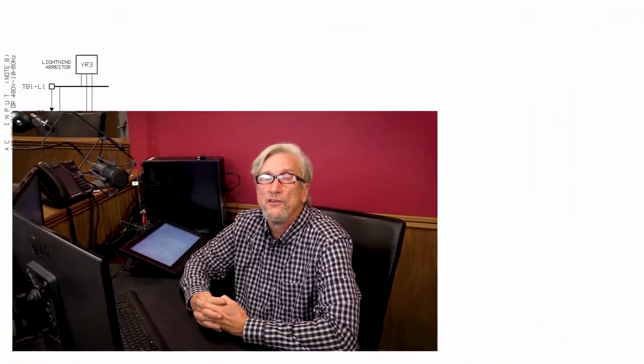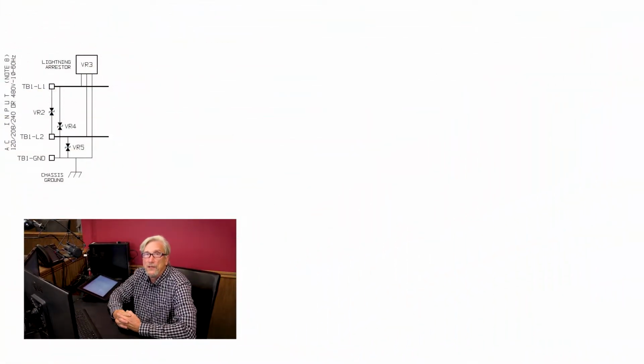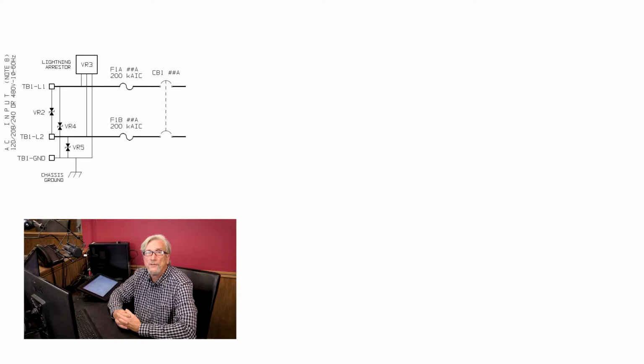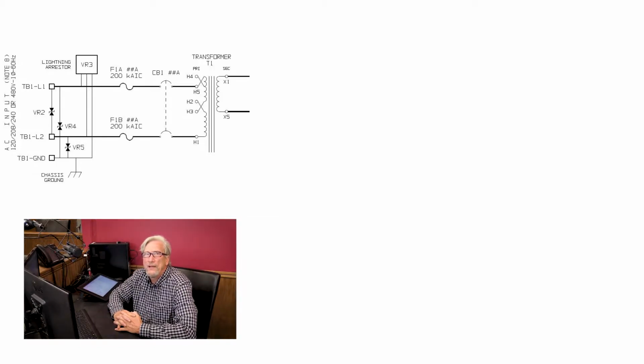Now we're going to talk about all the different components within the battery charger. First there's some way for the customer to connect to the battery charger, some I/O connections. The next thing is usually some sort of protective device in case there's a problem, like a circuit breaker or a fuse. Then it goes to a transformer, and that's where we get our isolation. The primary winding is ohmically separated from the secondary, and we run the secondary of the transformer at the right voltage for that particular battery charger voltage.